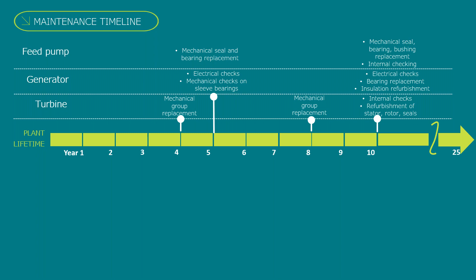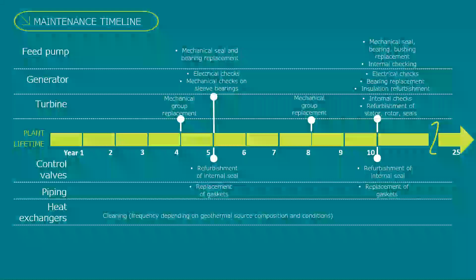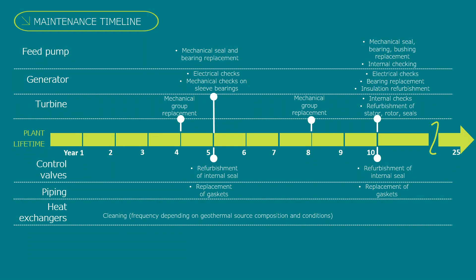Then about the rest of the plant, we have the control valves and the piping, which require the replacement of the gaskets for the piping, and the internal seals for the valve body and their actuators. About heat exchangers, it's worth mentioning that the heat exchangers are what mainly determines the stoppage for maintenance of the plants, and they require maintenance, which is essentially cleaning of the tube sides of the shell and tube heat exchangers. And the cleaning is necessary on the hot source, and the frequency may depend on the brine composition, on the heat source composition.